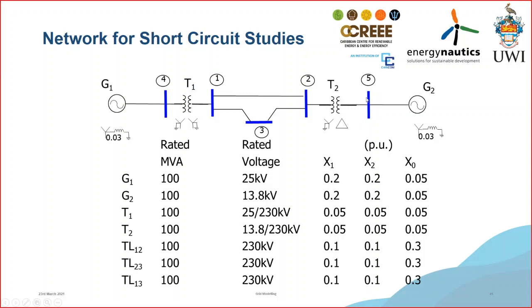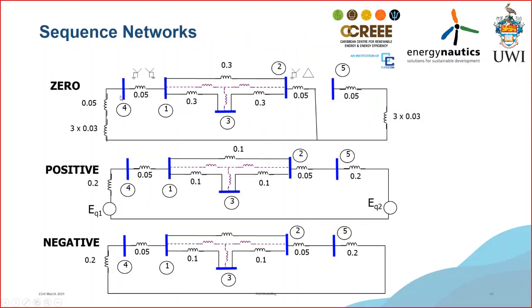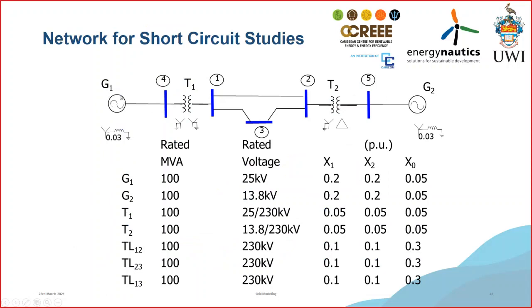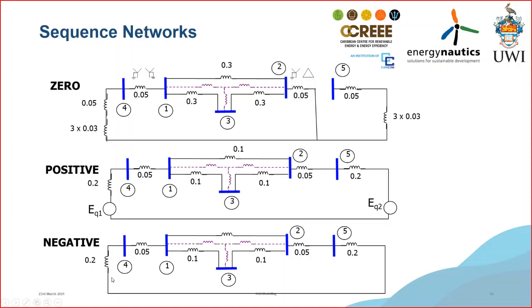Depending on how the earthing occurs on the system, your zero sequence network is going to change. So let's see how we can put this into networks. For the zero sequence network, I have my generator. The thing to note here is that in my zero sequence and my negative sequence, there are no voltages generated, because we assume that the only net voltages generated are positive sequence, by the generators. Your generators only generate positive sequence values. Therefore, there are no generated EMFs in your zero sequence and in your negative sequence. The positive sequence and the negative sequence look the same in terms of how they are constructed. The only difference is that you have a generated value, which is the EMF of the positive sequence network, but there is none in the negative.